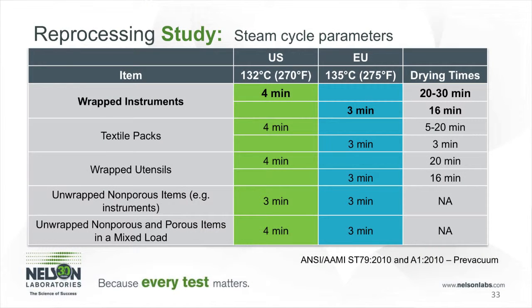Here's an example of the set parameters that are utilized for steam sterilization. On your left, I have the most performed U.S. cycles and the most performed EU cycles. A lot of our medical device manufacturers that are submitting for regulatory approval in both the U.S. and EU are performing a cycle that is kind of in the middle of both these two, and that is we're performing a validation for a 132-degree cycle for 1.5 minutes as a half cycle. Therefore, they only have to perform one validation cycle, and then the cost is cut in half because of that. So that's a very good way for a medical device manufacturer to save some money and perform the sterilization cycle for that medical device.